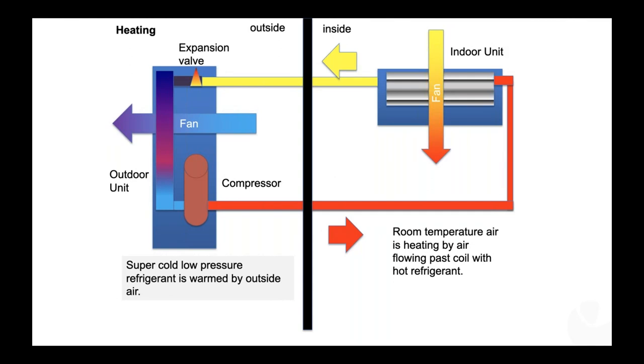And so it depends on the price of electricity as to what the cost of operating the system will be. But even at what's typical for most of New Hampshire, around 16 cents a kilowatt hour, on a seasonal basis, it translates into something akin to $1.50 or $1.60 a gallon number two heating oil. So it's very, very inexpensive. Now, it's less expensive to operate heat pumps when it's warmer outside than when it's colder outside. But at the cost of 16 cents per kilowatt hour, it is always cheaper to run a heat pump than to use propane, no matter how you're burning it.